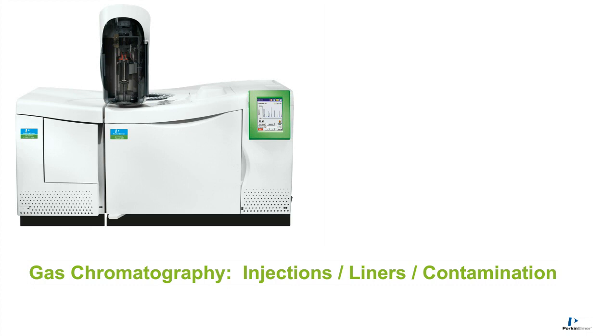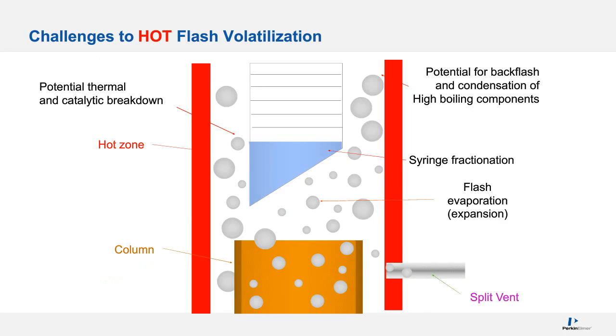Another way to test for activity, if you inject your components, do like a precision, inject your components several times. If they start to increase in intensity and then level off, that's usually indicative of an active site, because what you have been doing is with each injection, you're covering that active site until there are no more sites available for the compound to attach to. Unfortunately, that way of deactivation only lasts usually a day. But I know some of my labs that do mercaptans, they do three injections of a high standard, a blank, and then they start running their samples every day, because that's enough, and mercaptans are very active components. They stick to a lot.